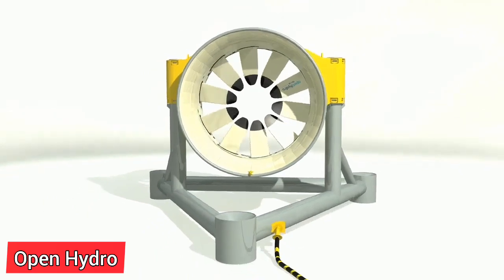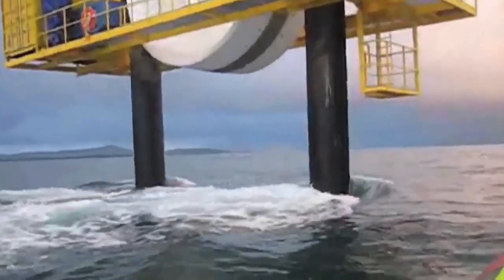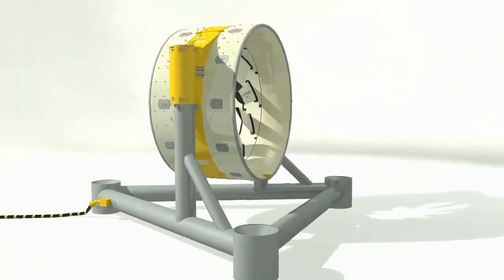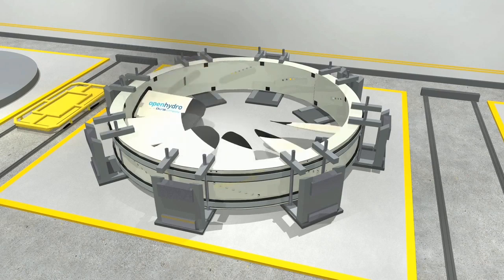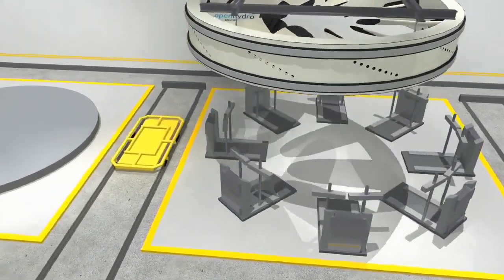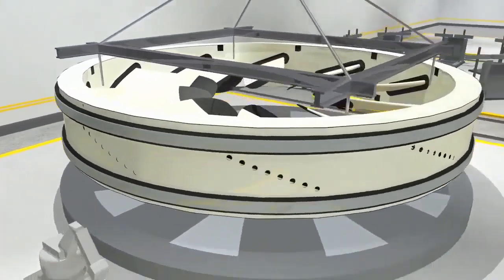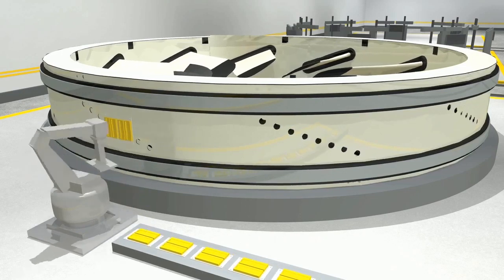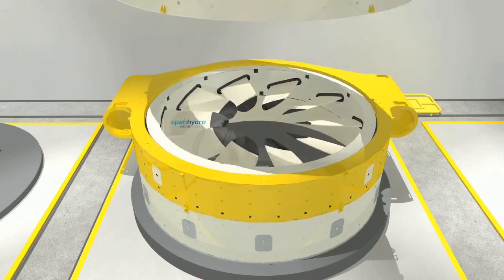The Open Hydro device generates power by using the inflow and outflow of water at low and high tides, with a turbine diameter of 16 metres. The igus E-Chain 4040 protects deployed motor and signal wires during the turbine's rising and lowering motions and against adverse environmental conditions. The travel distance, both vertically above and underwater, is about 20 metres, with the robust E-Chain guided in a steel trough. A plastic chain was the only viable choice, as a normal metal chain could not withstand the combination of mechanical demands and the marine environment, making maintenance on the open sea unnecessary.